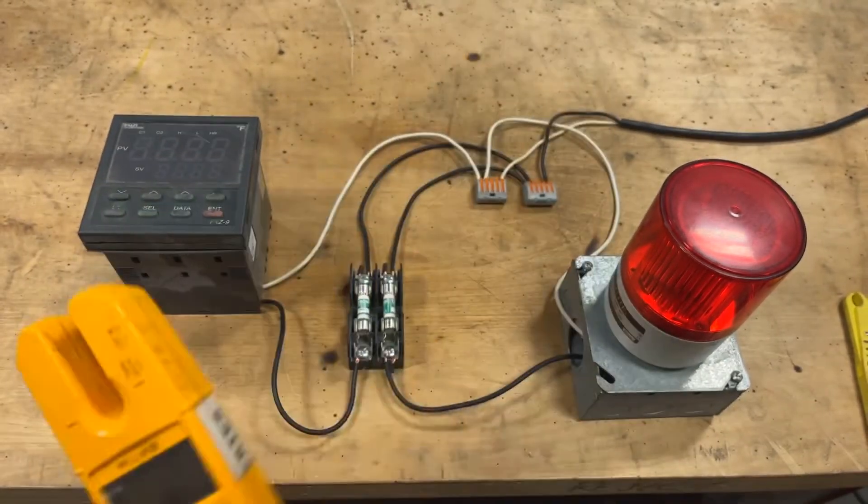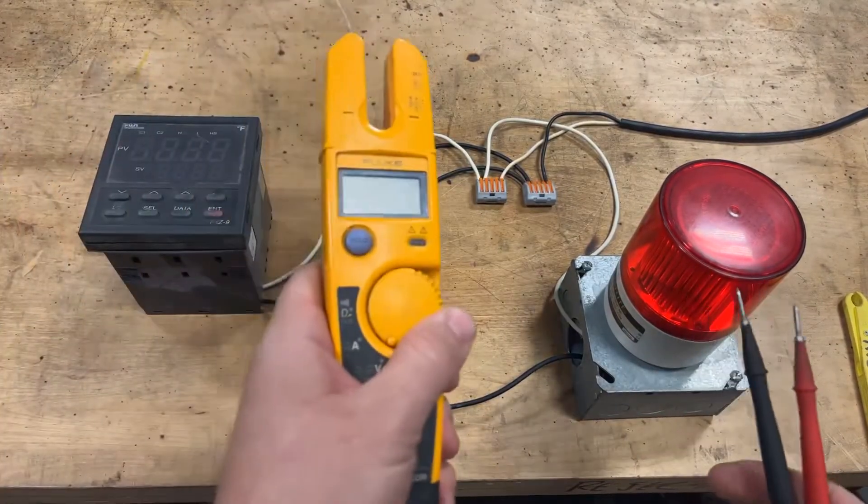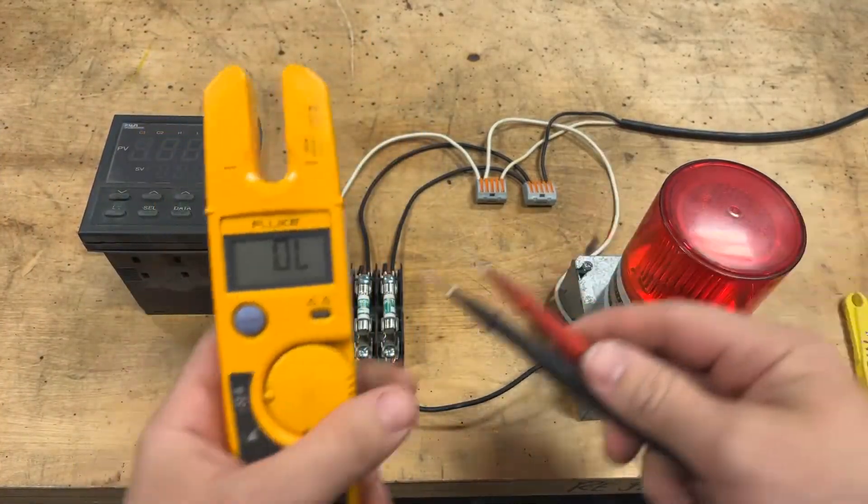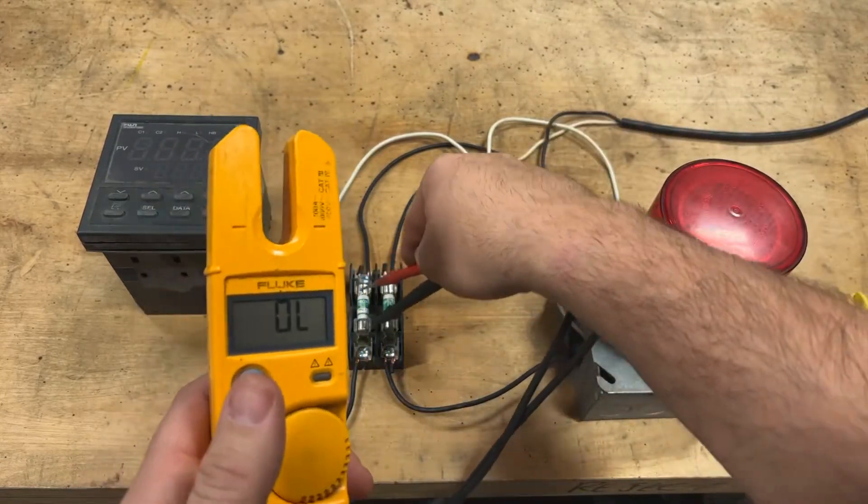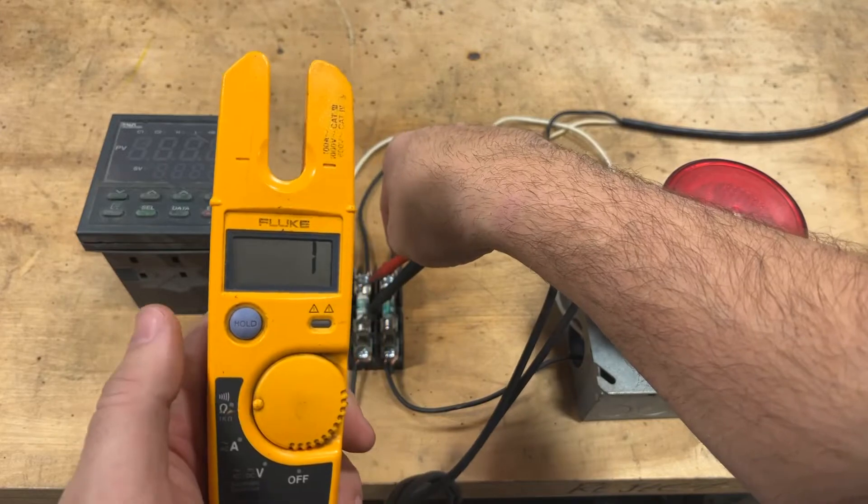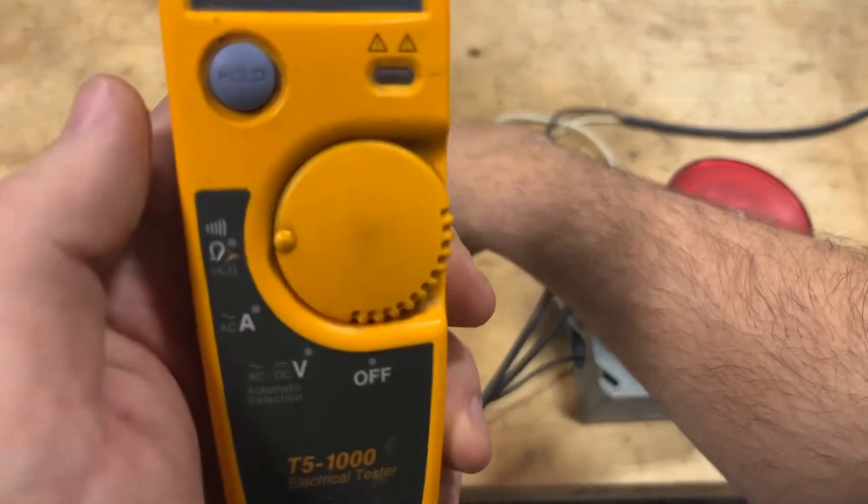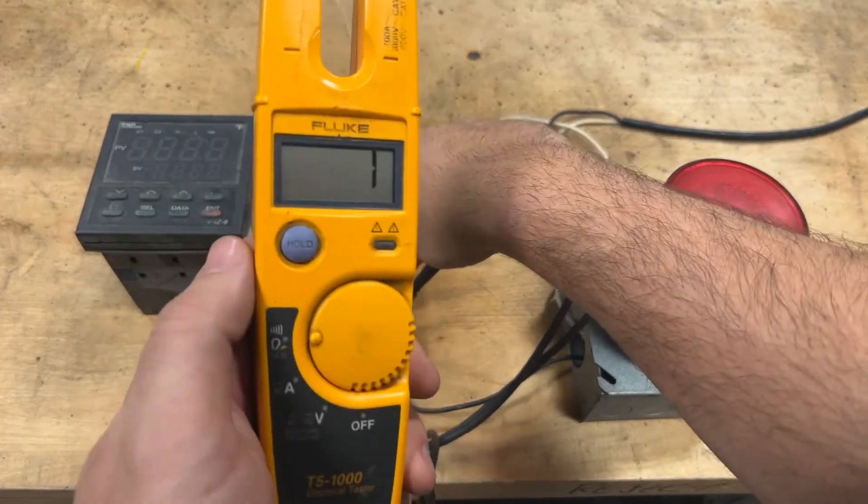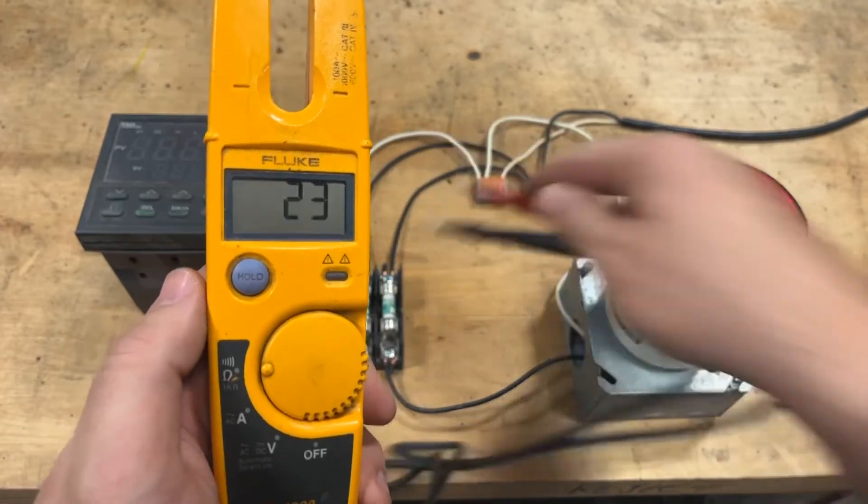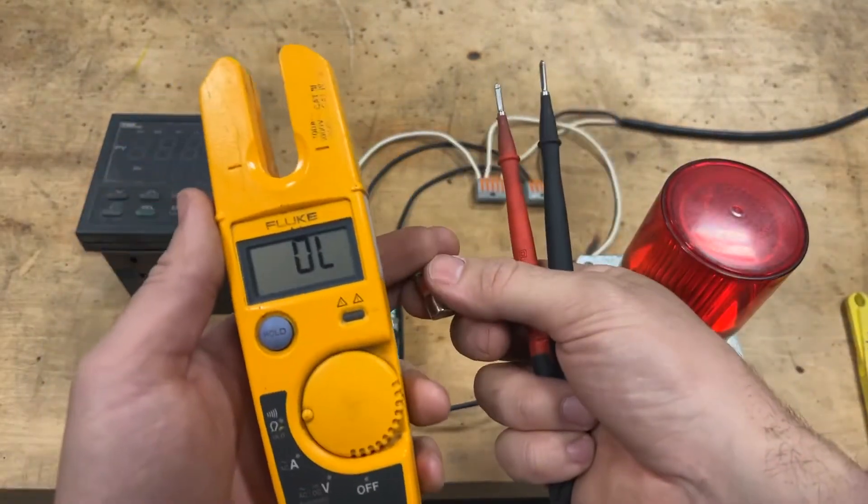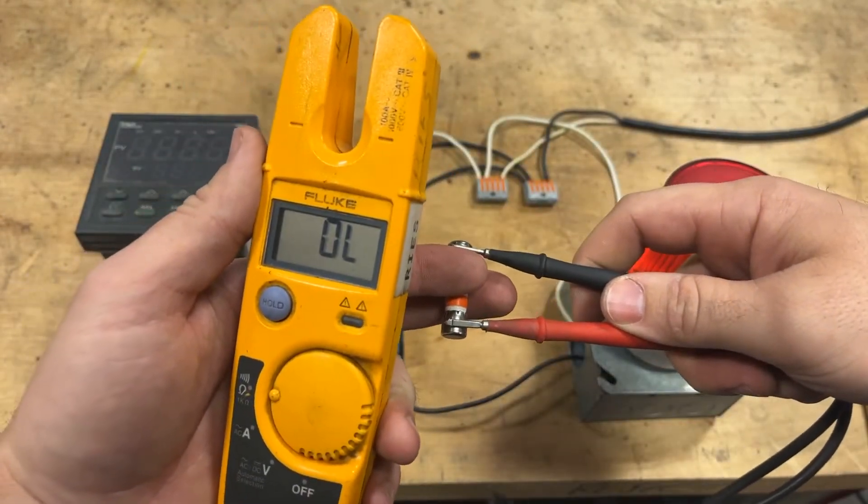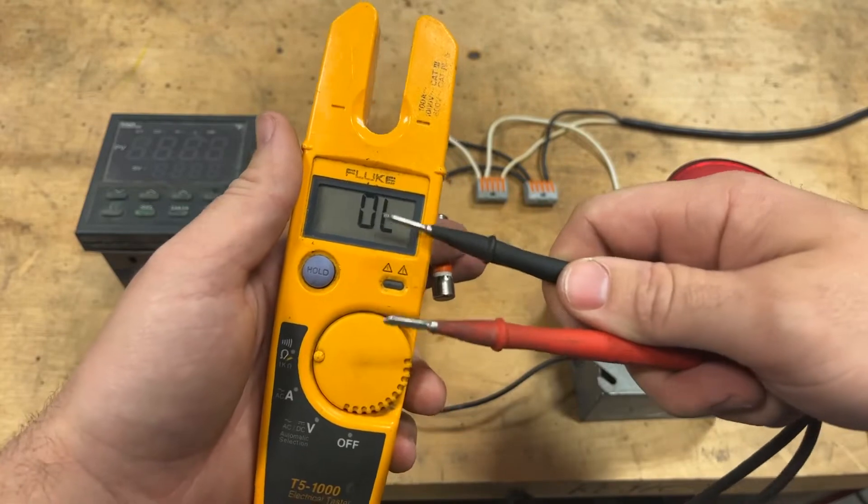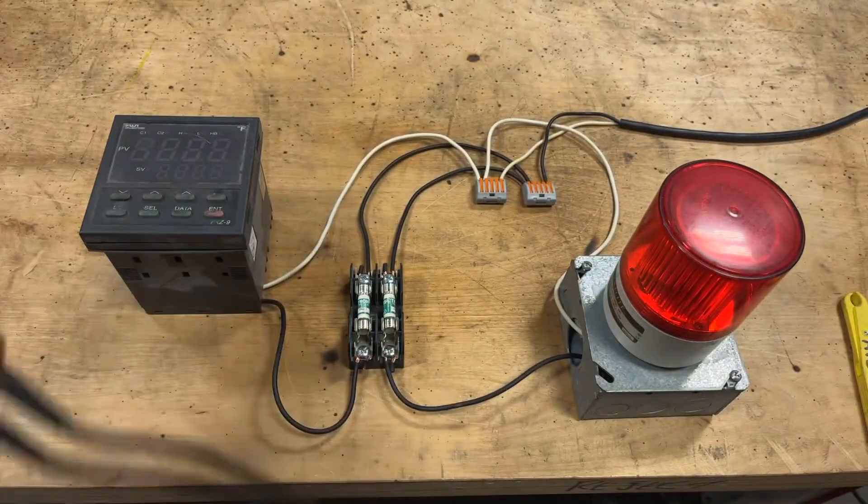So this particular circuit is dead right now. Let's check these two fuses in the block here to see if they're any good. See? I get a value on the screen and I get a tone on the meter letting me know that these are good. A bad fuse, exhibit A, will continue to say OL - out of limits, no good, out of freaking limits.